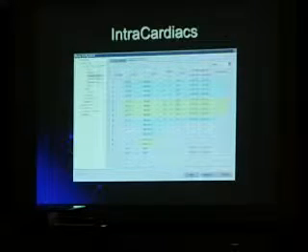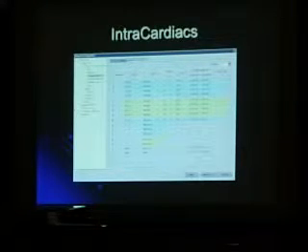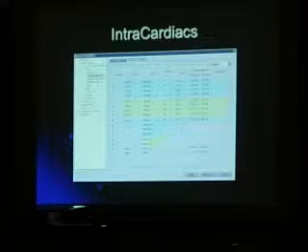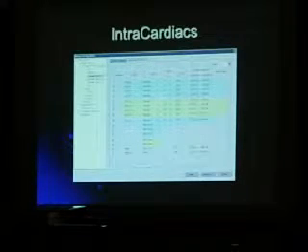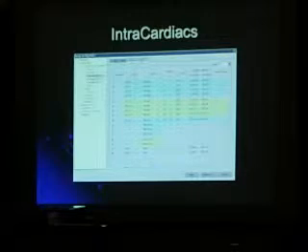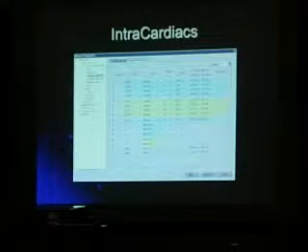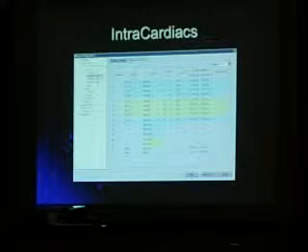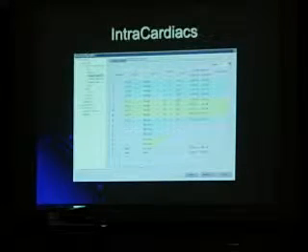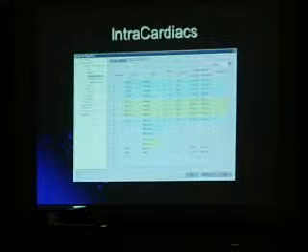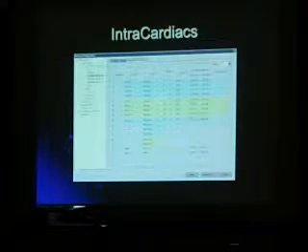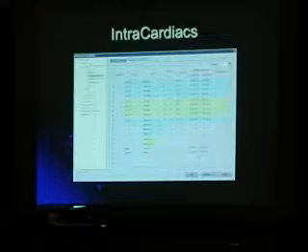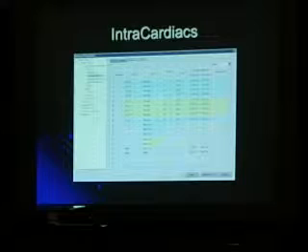So one of the things that we always do is low number to low number. I'm plugging in my RV. We already said that we're plugging the RV in at 17, 18, 19, and 20. So 17 is the lowest number. Distal number 1 electrode is the lowest number. They go together. 18, 2, 19, 3, 20, 4. Go low number to low number. It really doesn't matter to the computer if you switch it around, but then it becomes very difficult for you to figure out what's going on when you're trying to troubleshoot.